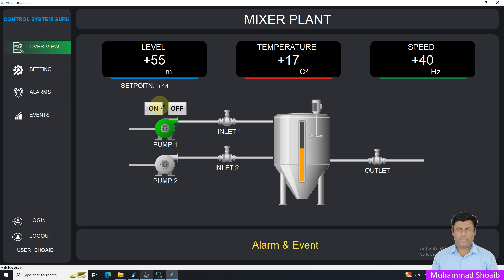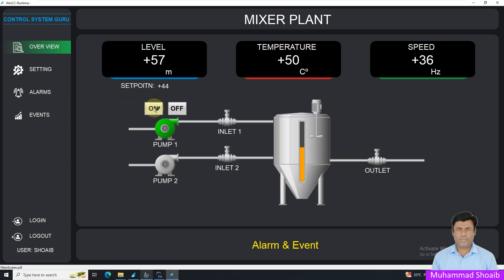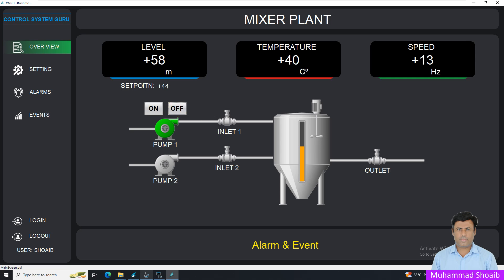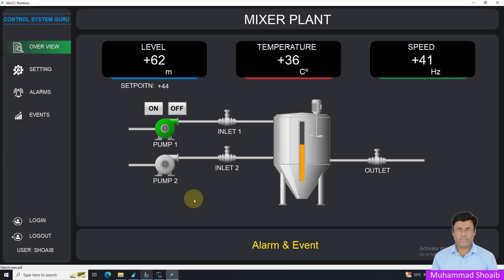Now I will receive values at the command address. Press the ON button — you can see address 1110 receives the value 1. Press OFF — the value is now 0. Like that, we can configure digital input, digital output, analog input, and analog output tags inside WinCC SCADA over the Modbus TCP protocol. Thanks for watching.